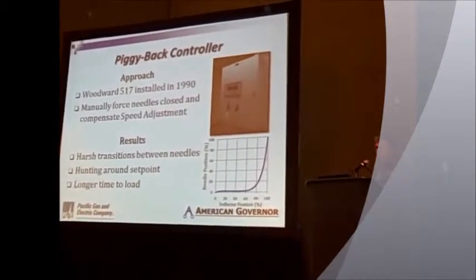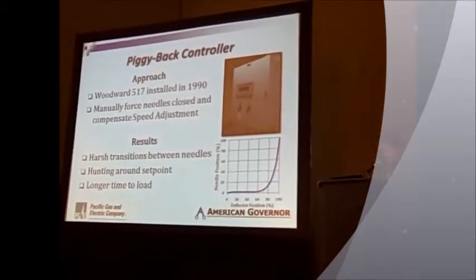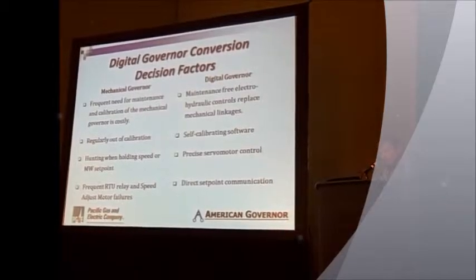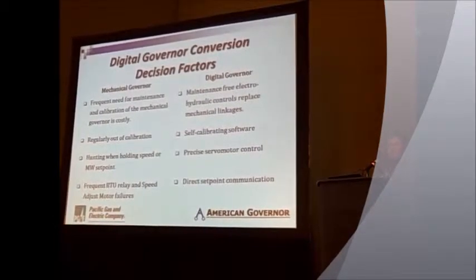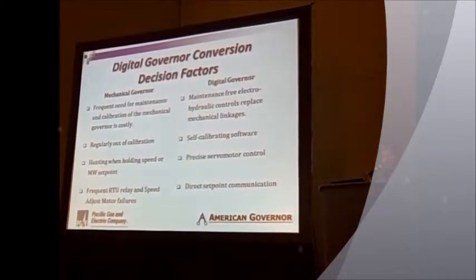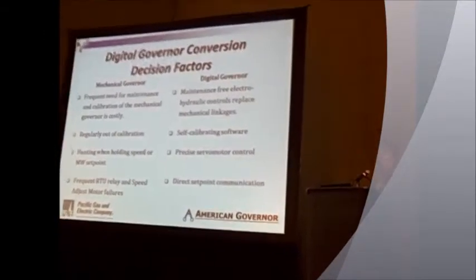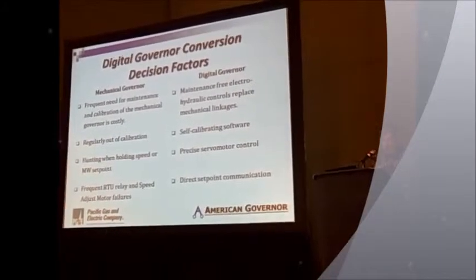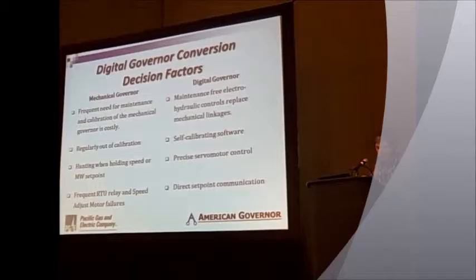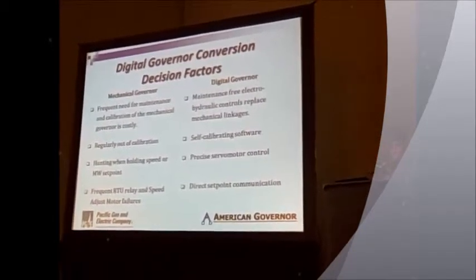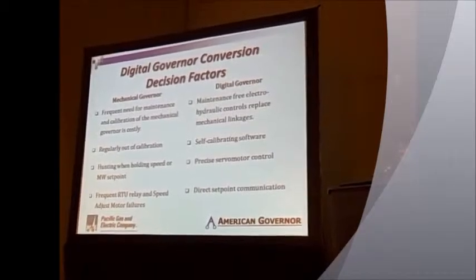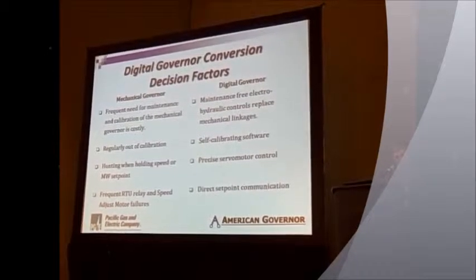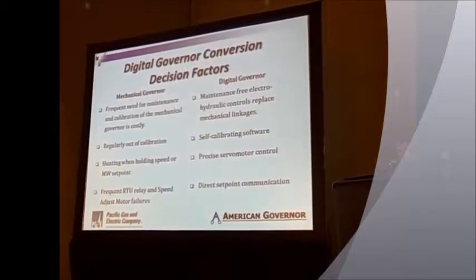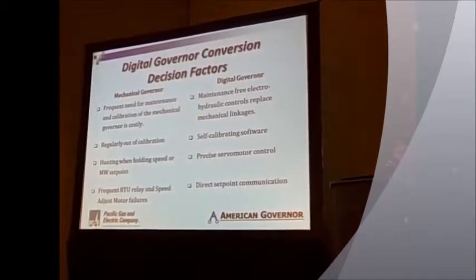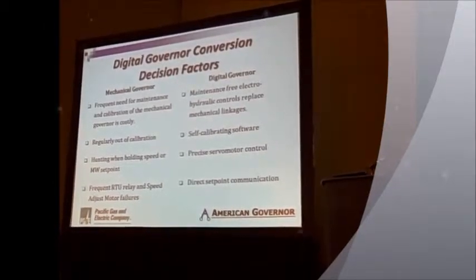Then in the early 2000s, we started seriously looking at a digital conversion. So we started looking at the digital governor conversion so that we could start eliminating some of the mechanical problems that we were having: the increasing maintenance costs, the frequent calibration requirements, the constant hunting, the difficulty paralleling. It wouldn't even hold load very accurately, and there was the constant replacement of all the relays and speed adjust motors. So that's when we made contact with American Governor, and they started helping us out, and that's where I'm going to give it to Matt, tell you what he did.